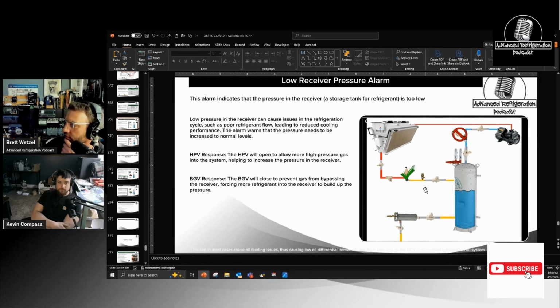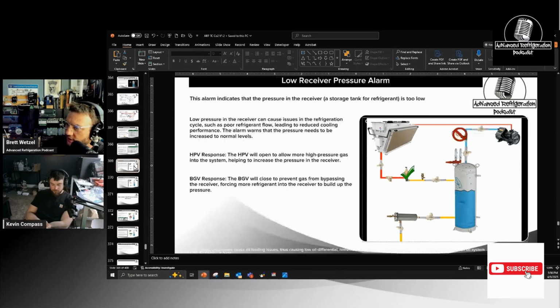So I have low receiver pressure, where basically if that gets too low. I've also seen where, because if you have a low receiver level, a lot of times this valve will try to open up, or it'll open up to try to maintain that pressure within there to basically raise it up. But I've also seen, what the hell was it? Essentially it was, the HPV was opened up way too far and wouldn't close. And the BGV was just it was during a hot summer day. And this valve was trying to do what it was supposed to do, except it was forced open, I think probably 75%. There's no really way to know exactly what it was. But because it was giving a high receiver pressure, it was basically opening up the BGV all the way the hell up. And then basically forcing the suction was just ridiculously high.